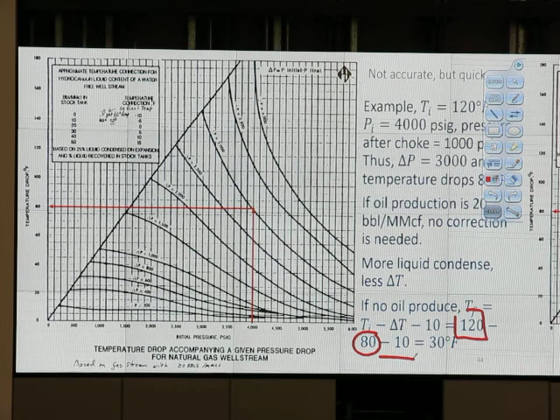Look at the case for no oil produced. If we don't have oil produced, the correction factor is minus 10. I calculate the delta T, which is 80 Fahrenheit without correction. Then I do minus 10, so 120 minus 80 is 40 without correction, but with the correction of minus 10 it becomes 30 Fahrenheit. So if we don't produce any liquid phase at all, the temperature will drop more. If we produce some liquid with it, the temperature will drop less.